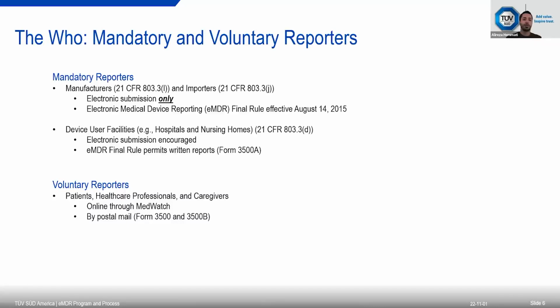So in terms of these mandatory reporters, manufacturers and importers now are required to submit MDRs electronically. And they use the eMDR final rule, which became effective on August 14, 2015. Device user facilities are encouraged to use the electronic submission form, but they are permitted to use written forms as well.